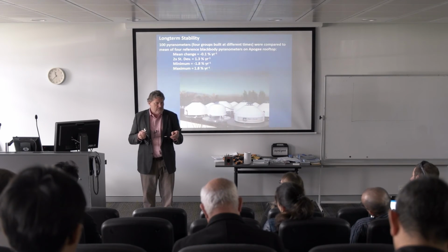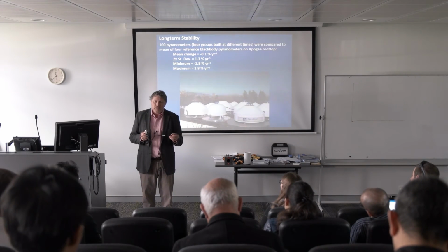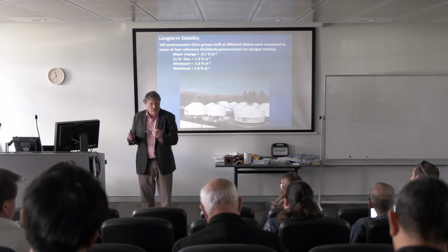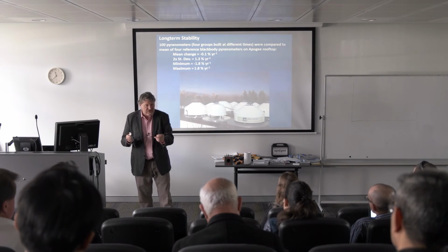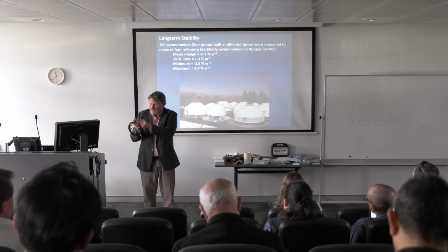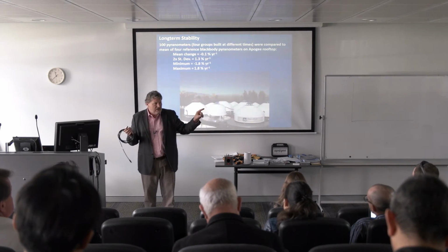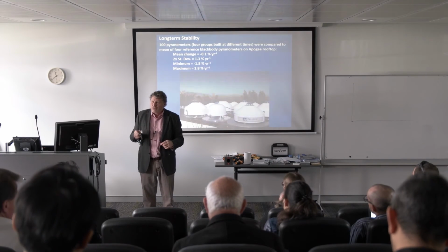Usually people write specifications for the cable, and the first obvious one is you want it to be as waterproof as possible, otherwise moisture starts to get in. The signal, even though the sensor is perfect, is not getting accurately to the data logger.